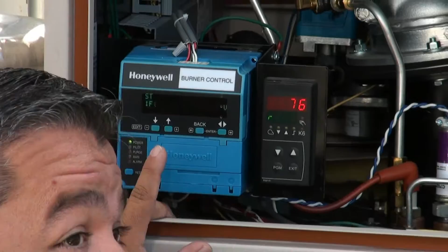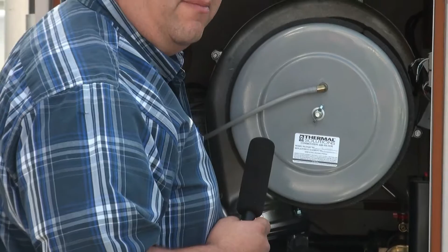So how do you know what percentage the boiler's at? That's in the VFD in the back. That's the fan though, right? Right, that's the fan, and that's how you modulate, the VFD, fan and the gas valves both mounted at the same time. Yep. So you'll be able to see it, and you'll see the flicker. When you look in here at the heat exchanger, when it's running 100%, it's bright orange. When it's below that, you'll see it dim down. Does the pilot system stay active? Stays active all the time. Okay, except for the spark. Except for the spark. Yeah.